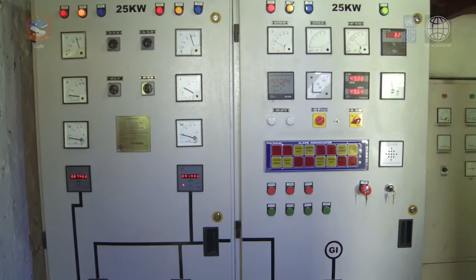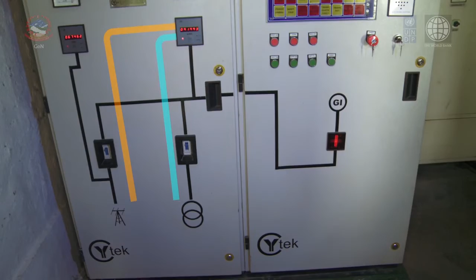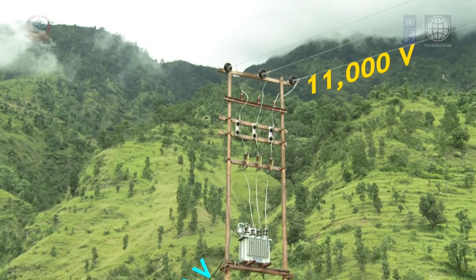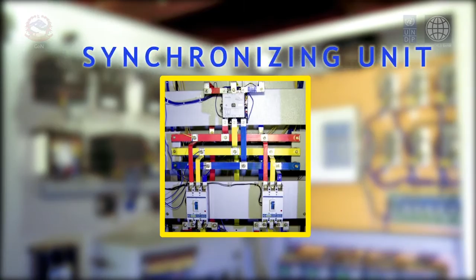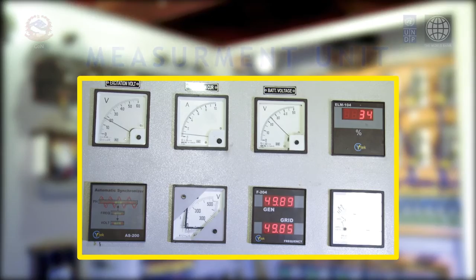The system has a provision of distributing the generated power from the microhydro plants either directly to the local villages as before or to the microhydro interconnected mini-grid after stepping up from 400 volts to 11 kilovolts. This advanced control system, which consists of different essential units including governing unit, synchronizing unit, protection unit, and measurement unit, made possible to interconnect all the microhydro plants for parallel operation.